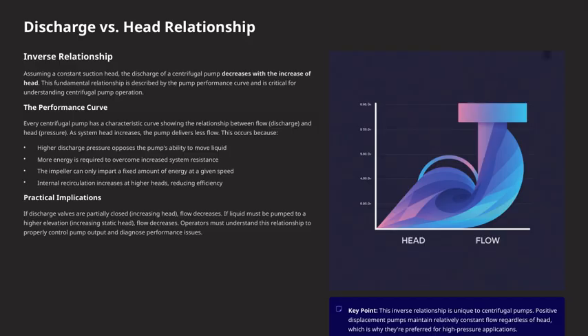Why does this happen? Well, higher discharge pressure opposes the pump's ability to push liquid forward, requiring more energy to overcome the increased resistance in the system. Plus, the impeller can only impart a fixed amount of energy at a given speed, so it can't continually increase flow when the head rises. Also, at higher heads, internal recirculation within the pump tends to increase, which actually reduces overall efficiency.